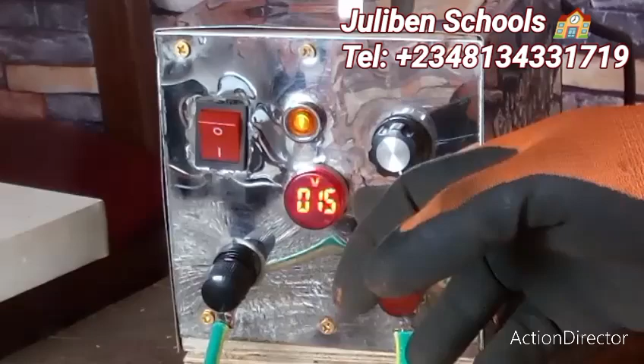If I take it to the lowest minimum, it seems to go up because it's almost at 0 voltage. So I'll take it up again and it picks up, this is 16, quite very low. If you take it lower than that, there's no voltage, so it cannot pick up. At this point it comes up, and this is the highest voltage, which is 223, between 220 and 230 volts.